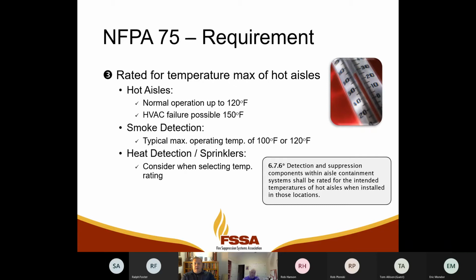If you look at manufacturer cut sheets for System Sensor or Siemens or Simplex, most smoke detectors are rated for either 100 degrees Fahrenheit or 120 degrees Fahrenheit. So we can exceed those temperatures, especially in some more modern data centers where there's less human interaction needed. If you go in a data center today, the people working in the data center doing software upgrades on the servers or swapping out equipment are wearing shorts and t-shirts. It's hot in there, and that's on purpose because they're running their data center to increase the inlet temperature, and we're picking up about 20-25 degrees across the server as the air passes by, and the equipment's being made so it can tolerate that higher temperature.